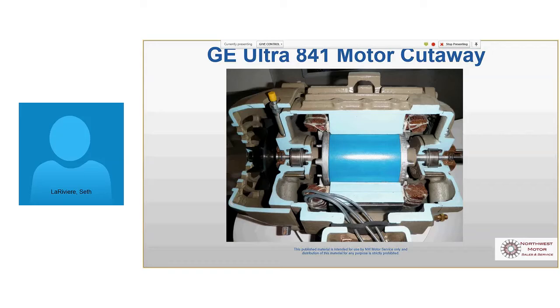Right. So that kind of becomes the tipping point where you go, I can take any NEMA motor off the shelf and it's probably going to be okay. At 75 horsepower, there's more application consideration. So we're going to be asking more questions. Anybody's going to be asking more questions specific to that application. And that's again pretty standard. NEMA standardizes a lot with electric motors from manufacturer to manufacturer. What they don't do is say here's where you need a roller bearing versus a ball bearing, or where you can go vertically or not. But we see those changes happening at about 75 horsepower for most of them.